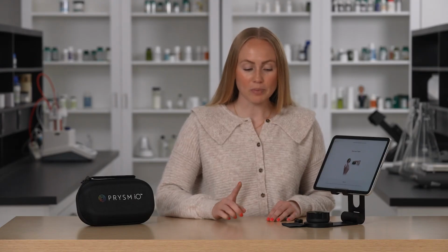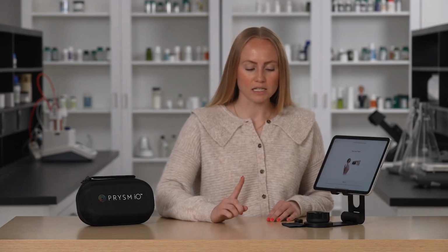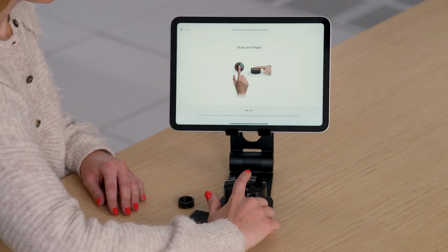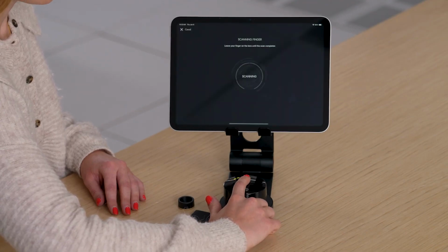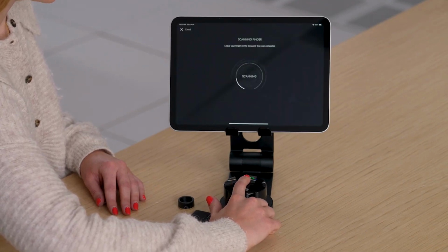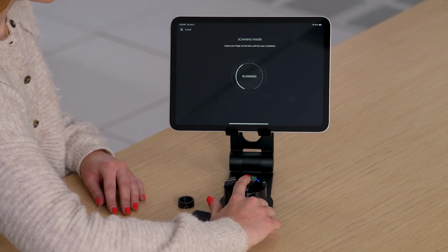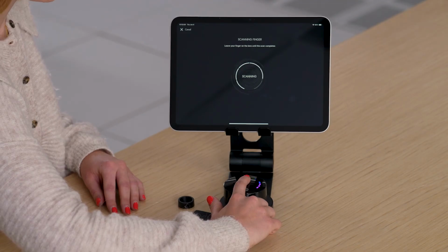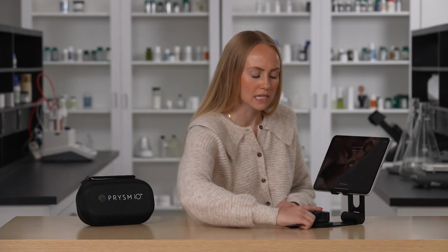Following the best scanning practices, make sure that your finger is placed covering the lens completely and that you have firm, even pressure over the lens. Make sure that there's no light leaking out of the lens. This is best performed if you are sitting to make sure that your arm doesn't move and that you have even pressure during the entire scan.